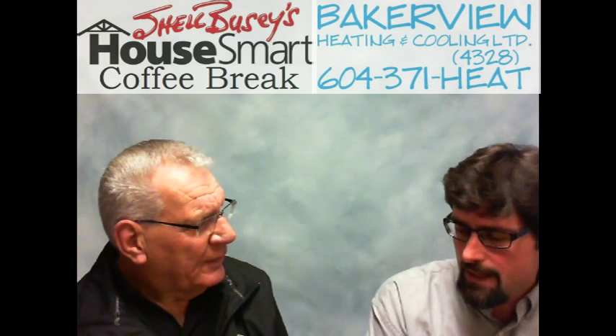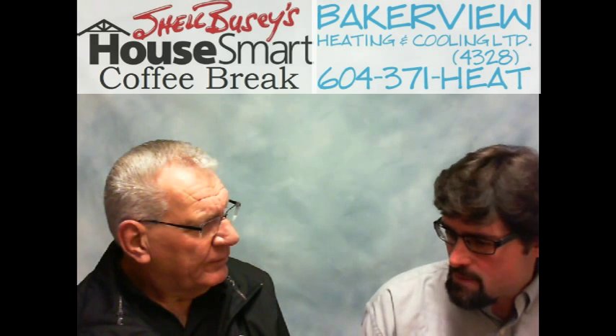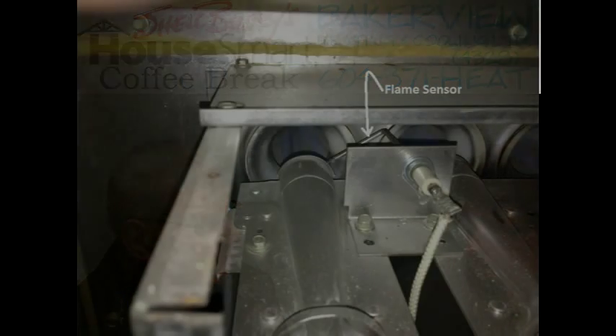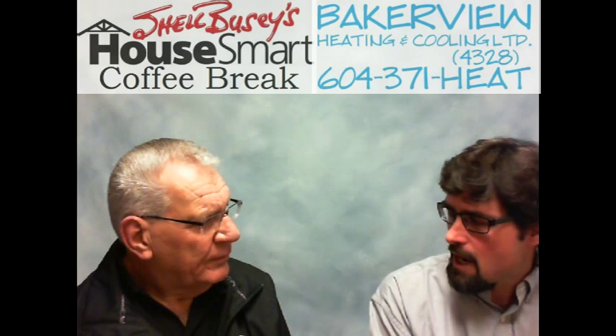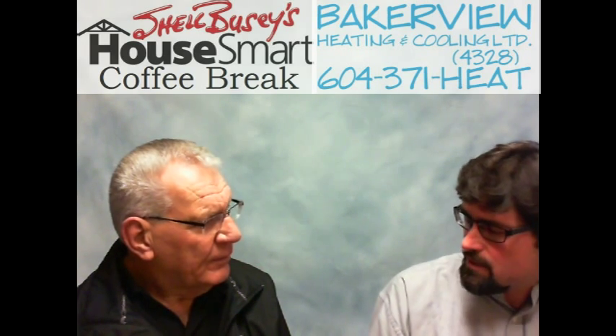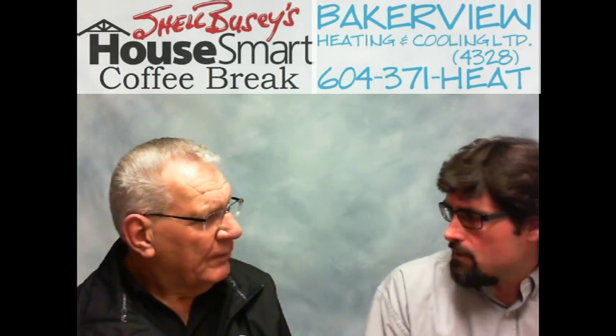They sure do. Every high efficient or mid efficient furnace has what they call a flame sensor, and that flame sensor gets tarnished, so it needs to be basically buffed up and cleaned. The runner bars on your burners have to be clean, because if that runner bar isn't clean, your flame isn't going to shoot across, and it's not going to hit that flame sensor. And if it does hit the flame sensor, and the flame sensor is tarnished, it's not going to sense, and basically you're going to a lockout and you have no heat.